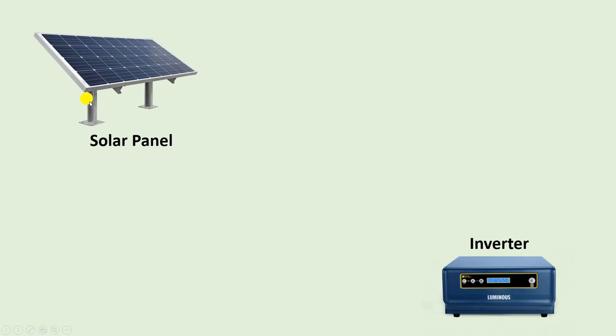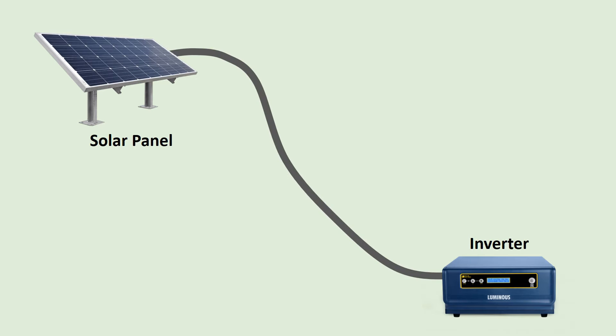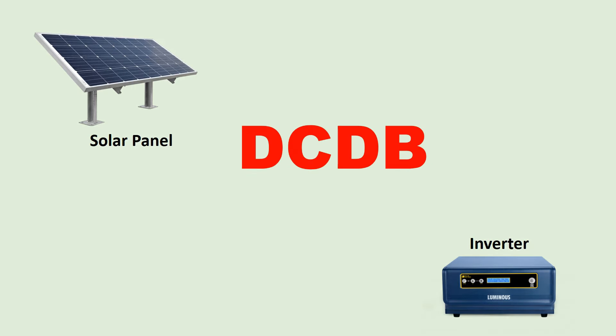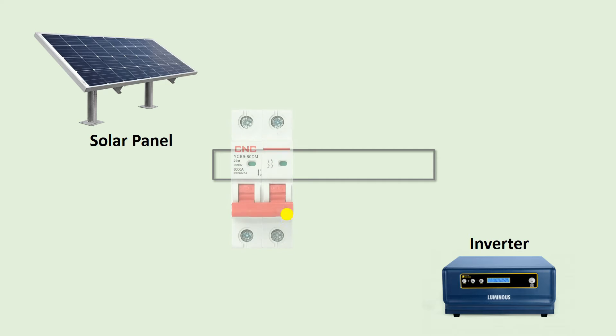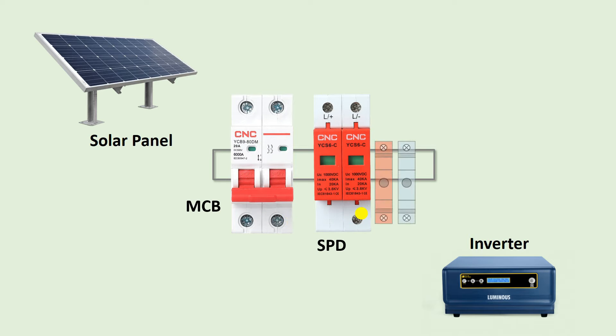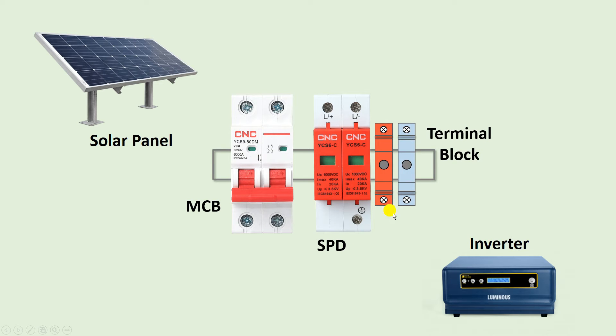Friends, if you do connection of solar panel in your home, at the time of connection you connect power supply of solar panel directly with inverter — but you should not do this. What you have to do is connect the power supply from the solar panel with a DC DB. Inside the DC DB, you have to connect a MCB, after this one SPD, and after this two terminals.